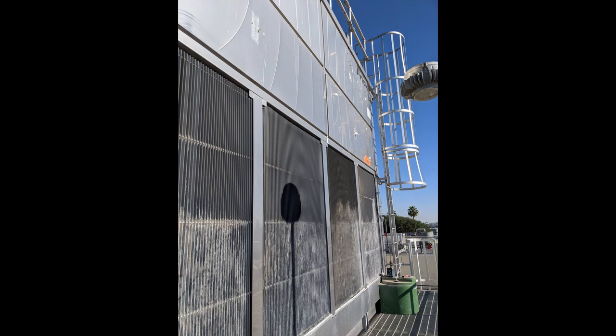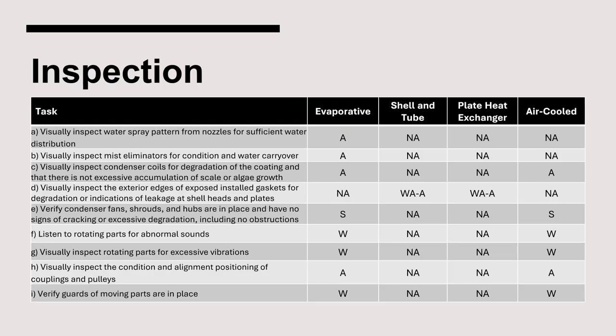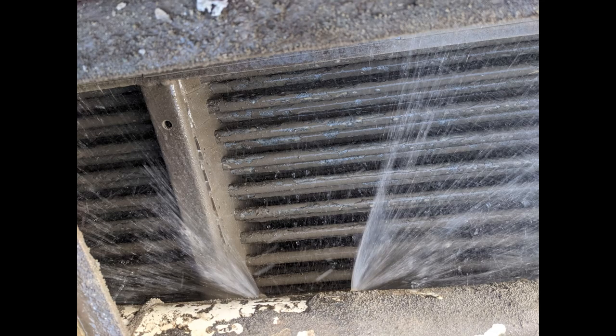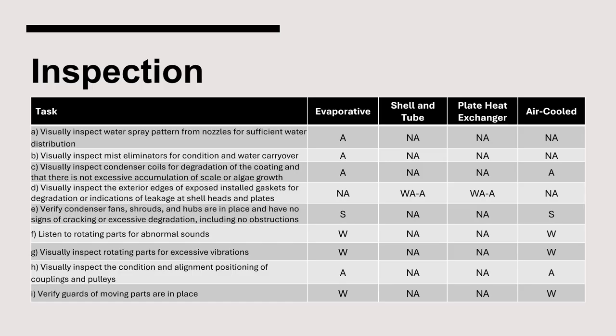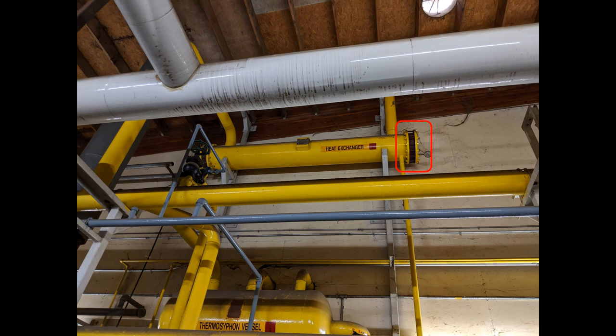Excessive scale buildup is visible on these mist eliminators and should be cleaned to ensure it doesn't worsen. Visually inspect the condition of the galvanized coating and scale buildup on condenser coils. These condenser coils are coated in scale, which reduces the efficiency of the unit. Next, visually inspect the exterior edges of exposed installed gaskets for degradation or indication of leaks. The edges of the gasket installed on this shell and tube condenser can be visually inspected at the heads.